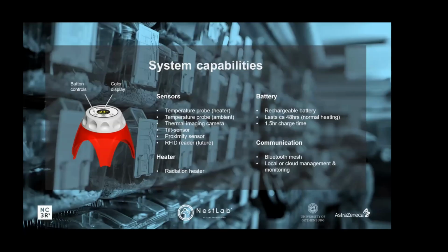The capabilities of this system, I can talk a bit about that. So here you see a NestLab on the left. We have 3 buttons to control temperature up and down and enter the menu. There's a simple color display. We have different temperature sensors. We have a temperature probe near the heater.